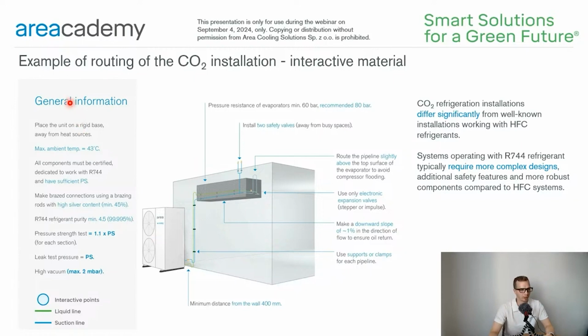In the general information section, you will find information about how to place the unit properly, what is the maximum permissible ambient temperature at which the unit can operate, which material to use for making brazing connections, what should be the purity of CO2 refrigerant, what pressure value to use for the pressure strength test and for the leak tightness test, and what is the required vacuum value before charging the refrigerant into the system. And many more information regarding the distances, supports, pipeline slopes, insulation, velocities of the refrigerant in the suction or liquid lines, and so on. I highly recommend you visit our Areacademy website and read this material in detail.